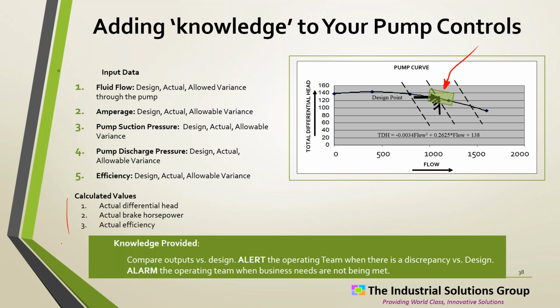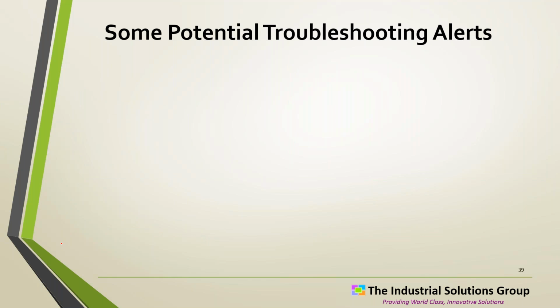If I'm a little bit out, I would want to alert the technician team that something's not right here. It's starting to go bad, so it can be put on a maintenance schedule, an operating schedule, and we're trying to alert people, give them time to respond, get it back at design before there's an alarm, because alarms are usually bad. Alarms mean I don't have enough pressure to keep the process running. I don't have the right temperature in order to make quality products. So we're trying to build a second piece in, a flag, an alert to the operating team and maintenance team.